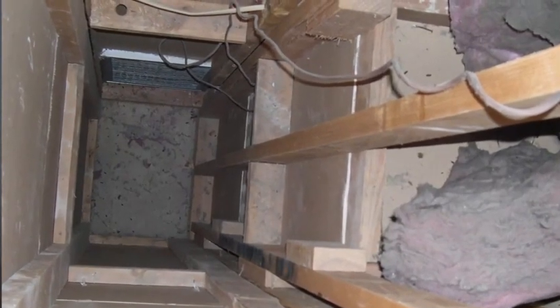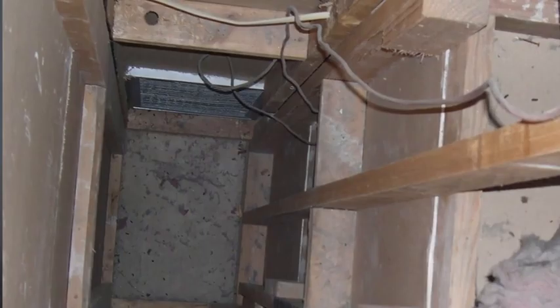Alternatively, the chase type return can often be upgraded to actual ductwork at an additional charge. One approach is to drop new ductwork down the original large chase. So those large box or chase examples are usually fixable. Building cavity returns cause more significant challenges when they are very extensive and you can't get into them.